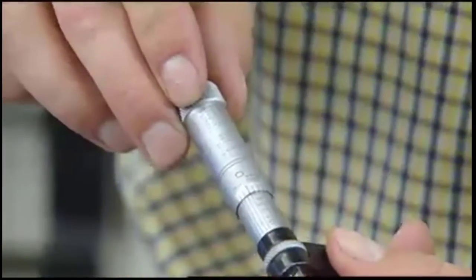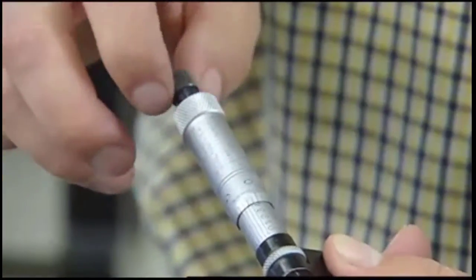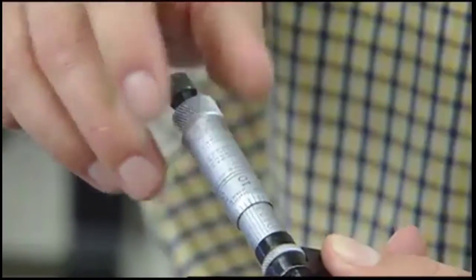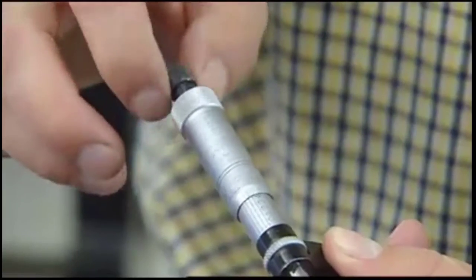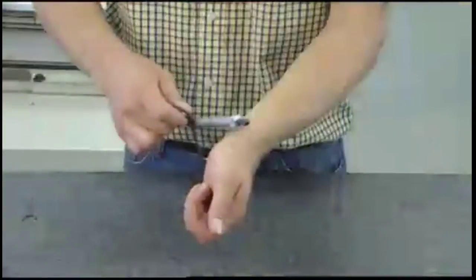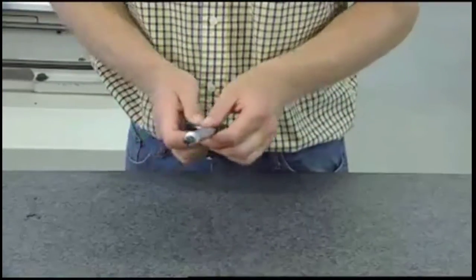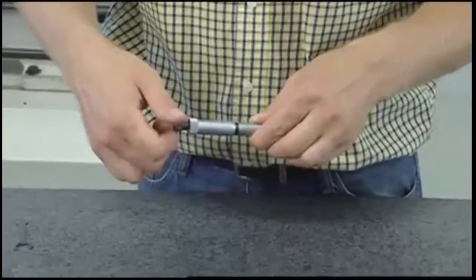Next, check the spindle for smooth, free rotation. The fit of the spindle threads should not be too loose, but should rotate effortlessly. If the spindle threads feel loose, open the micrometer spindle far enough to expose the threads.